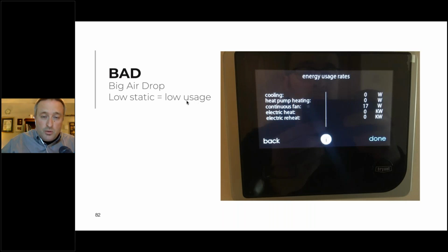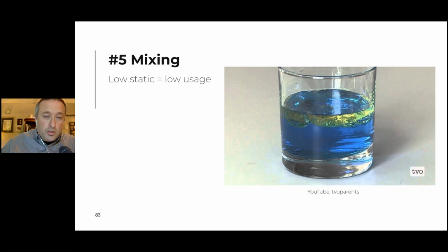If you do a good job of keeping the static pressure low inside the systems, you can really get very low draw. So with low static, you get low usage, and you get mixing for free if you leave the fan on all the time.